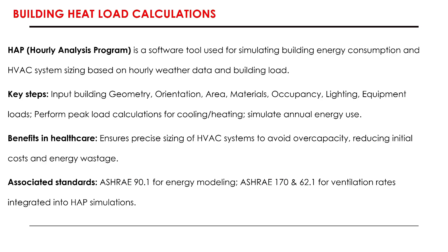These heat load calculations are essential, which Architect Nandini covered very well, saying it's important to know the orientation of the building, how much elevation has to be treated, and other things. These inputs are very much considered by engineers in making this successful, so that the benefit of doing this is to ensure precise sizing of the HVAC system in terms of tonnage, instead of using a thumb rule system that results in overcapacity or undercapacity of air conditioning - reducing initial cost and energy wastage in the future.